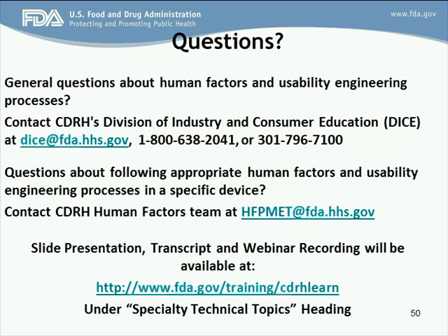Okay. I think what you would need to evaluate at that point is understanding the critical tasks of use. If you're expecting it to be somewhat like a training program, right, so that the first five uses are guided by a master user or something like that, then maybe that needs to be built into your understanding of your simulated use scenario. So that might be represented in a training type scenario within your summative testing. So again, thinking back to what the critical tasks are: what are the things where an error could be made that could lead to harm? And trying to effectively implement those within your summative study so that you can get a clear understanding of how your device supports those issues.